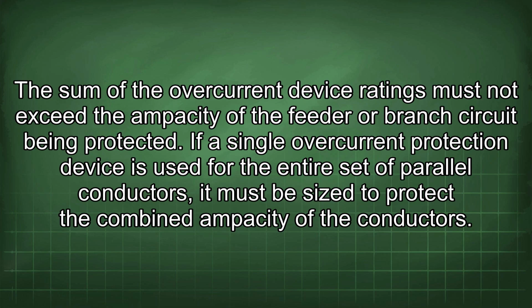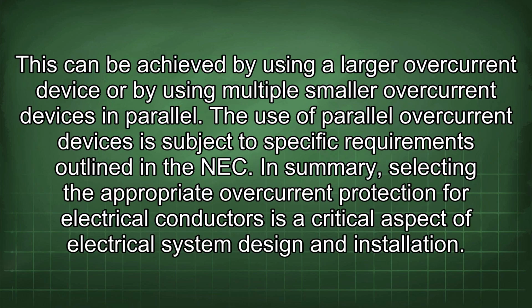If a single overcurrent protection device is used for the entire set of parallel conductors, it must be sized to protect the combined ampacity of the conductors. This can be achieved by using a larger overcurrent device or by using multiple smaller overcurrent devices in parallel. The use of parallel overcurrent devices is subject to specific requirements outlined in the NEC.